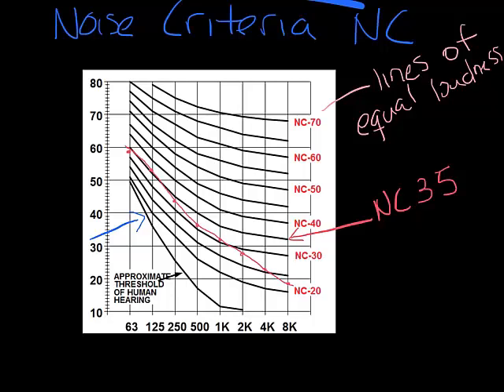Now I want to plot another sound curve. This time let's look at something that might be a diffuser. 29 in the first, 32 in the second, 35, 36, 35, 33, 30, and 28. Again, when you draw the line here, you can see that although it's a very different curve, it's about an NC 35 also. This is most likely a diffuser because you can see it peaks in the fourth band or so.